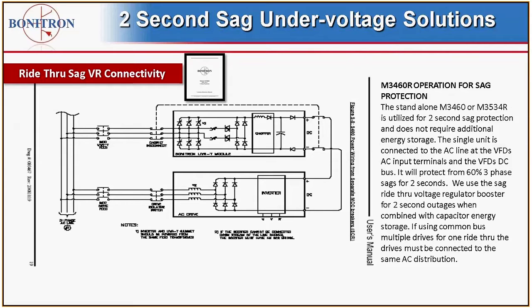Now some operation and functionality for the 3 different versions that we have, starting with ride-through sag, which is the least, I don't want to say complicated, but you only require 1 unit, and the unit connects directly to the AC line and the DC bus of the drive, as you see right here. These single units do not require any additional ride-through storage, but we can use this sag ride-through unit and add ultracapacitor energy storage. But the limitation of this unit is it can only work for 2 seconds. So it will only cover up to 2-second full outages, with ultracap energy storage.